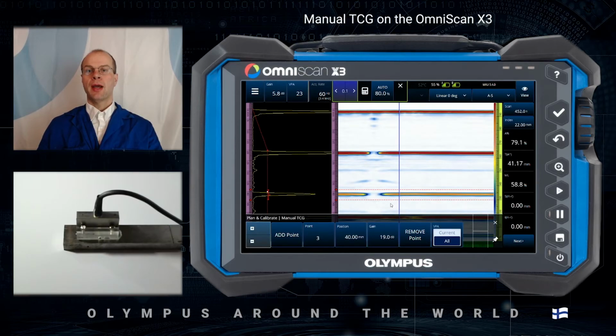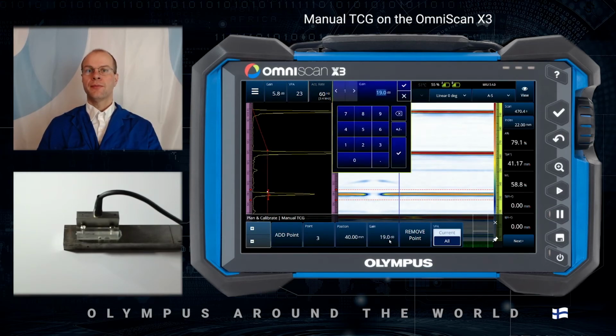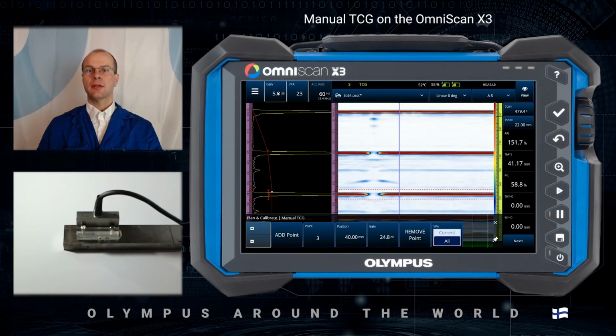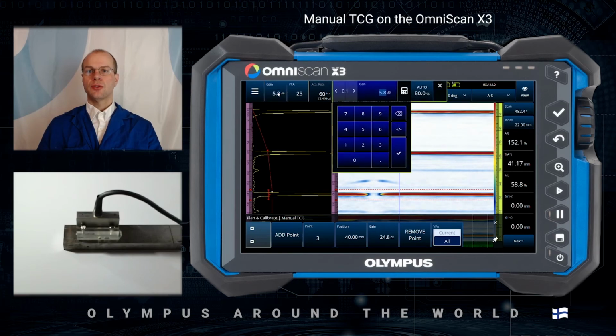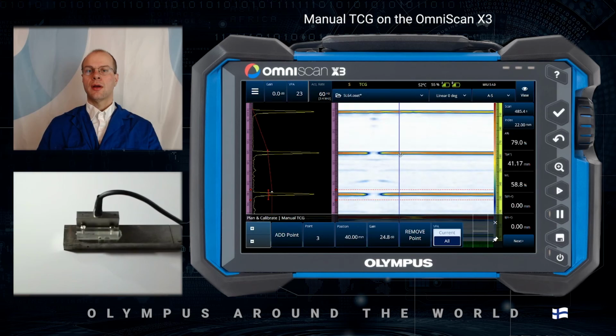So my TCG gain for point number three is 19 plus 5.8. So this is then 24.8. Good, and I will set this now to zero. And there we go. We have the second back wall at 80% full screen height.